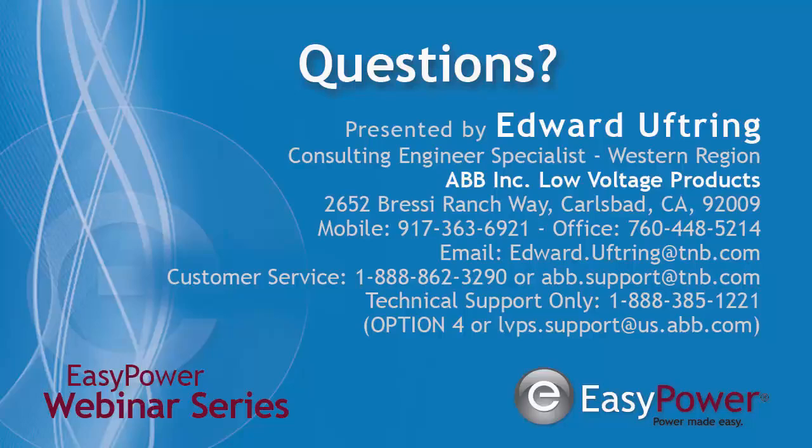If your panel is fully rated, does it mean that all circuit breakers, including the branch circuit breaker, must match their service interrupting current? So basically, when you're in your panel, the rule of thumb is that the weakest link is your current rating. So you can have an 800 or 1,000 amp breaker in that panel, a 2,000 amp breaker in that panel, but if you have a 35 KA MCCB sitting in that panel, it's only going to mark up to the 35 KA for that MCCB.